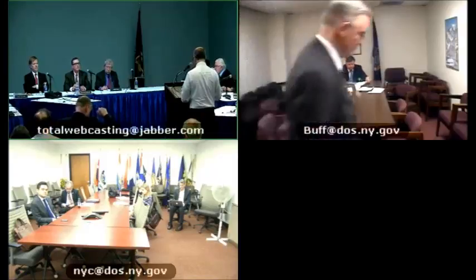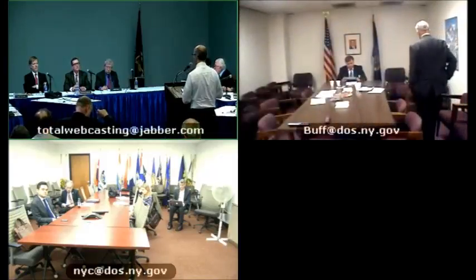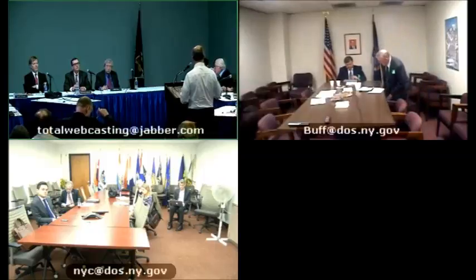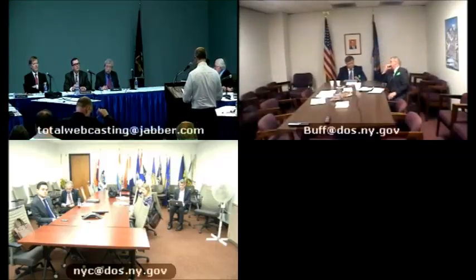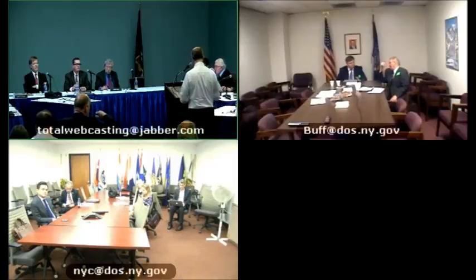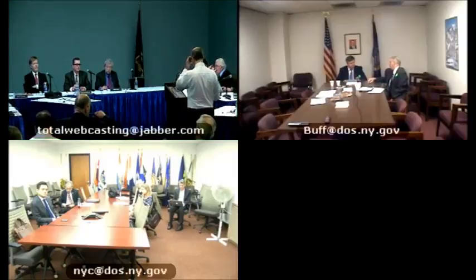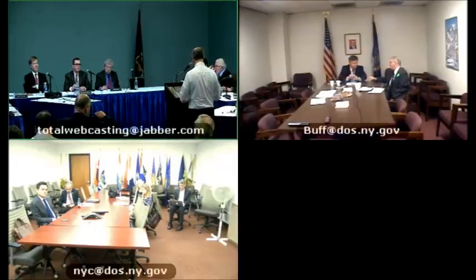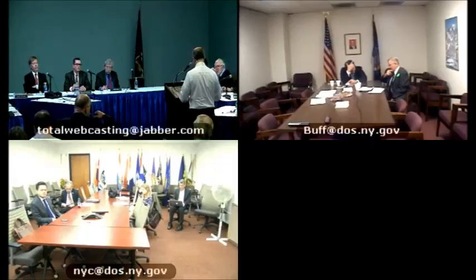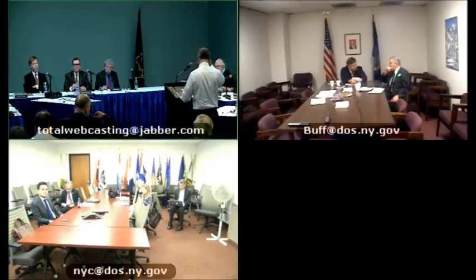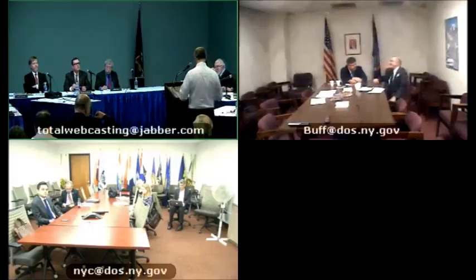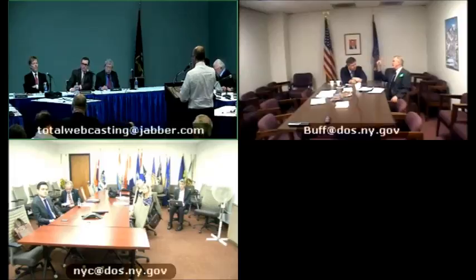Electric cooking appliances are exempt from requiring a type hood when they put out a limited amount of grease. Exhaust requirements for manicure and pedicure stations have been updated and revised and now require a source capture system for each station. A new section now recognizes use of inline dryer exhaust, which allows additional flexibility in location of the dryer. And I talked about balancing of the exhaust ventilation system. So any questions on mechanical? Any questions for John?